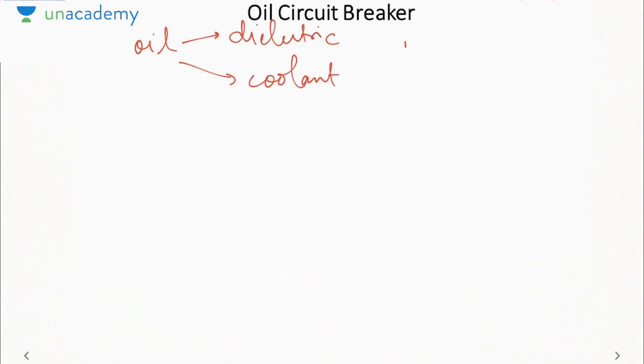So, first is your oil circuit breaker. It has oil between the plates of the circuit breaker. So, oil acts as a dielectric plus it acts as a coolant. These both functions are performed in case of a transformer. Usually, the transformer has some oil and that oil acts as a dielectric as well as a coolant for the transformer. So, here the oil will act as a dielectric between the plates of the circuit breaker because the plates of the circuit breaker are kept in the oil tank in case of a transformer.